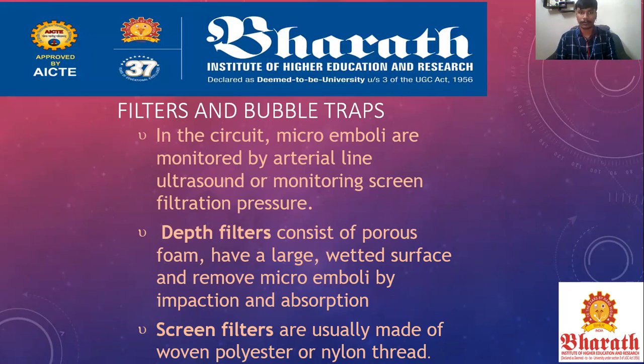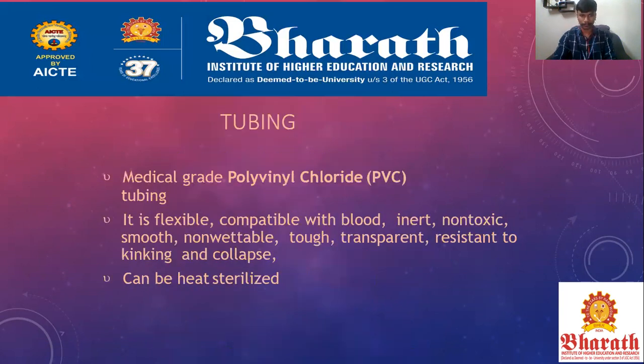Depth filters consist of many small holes, called microporous foam, having a large wetted surface as its structure, and are used to remove microemboli by impaction and absorption. Screen filters are components usually made of polyester or nylon thread, which are used to filter unwanted materials in the blood circulation.